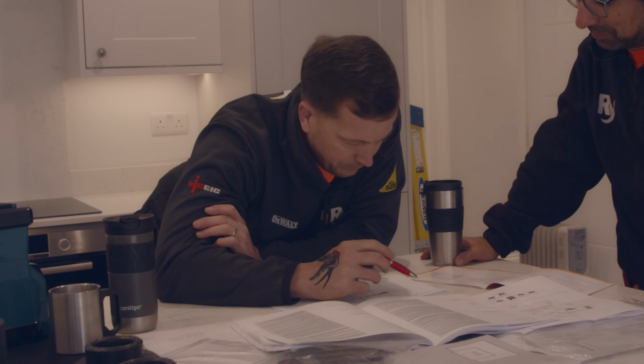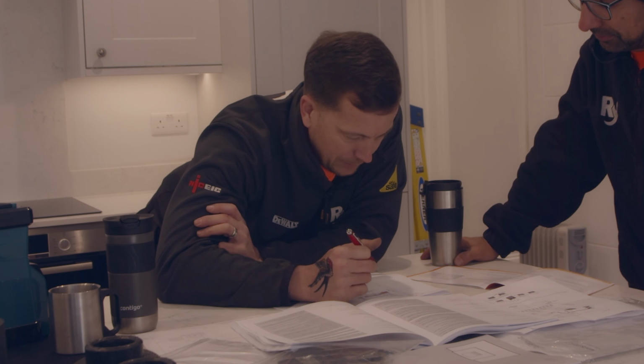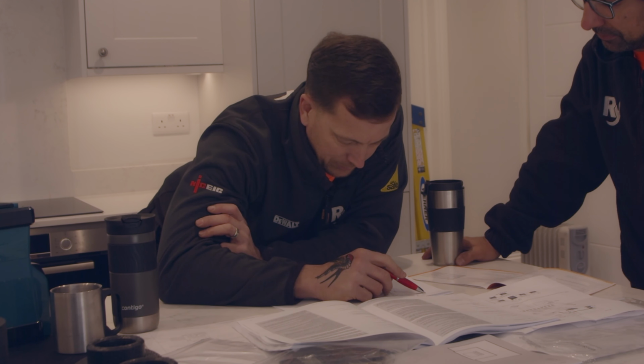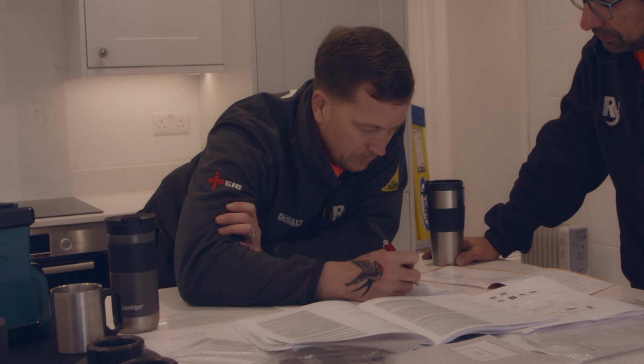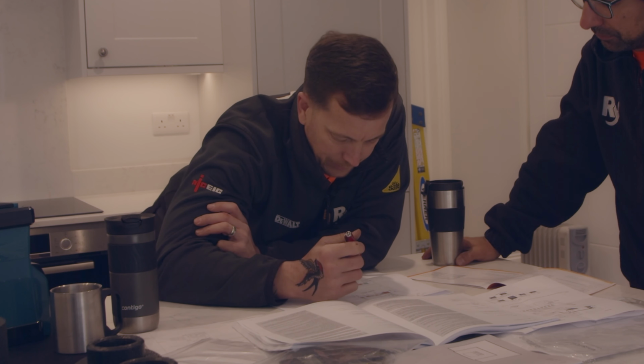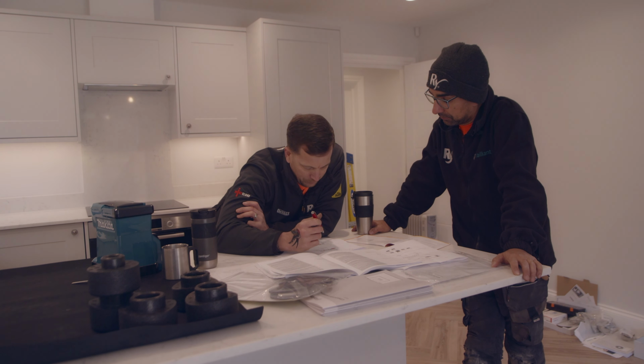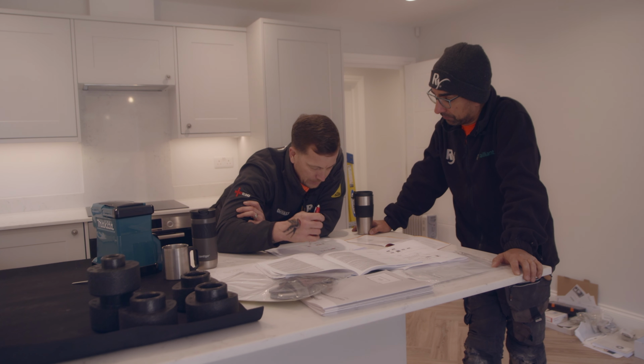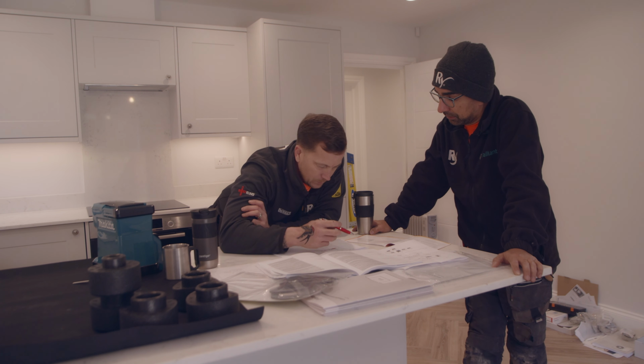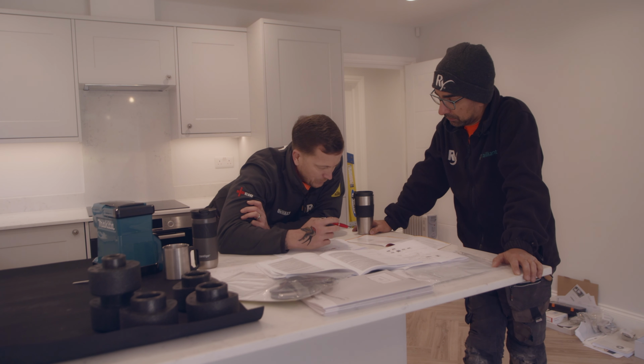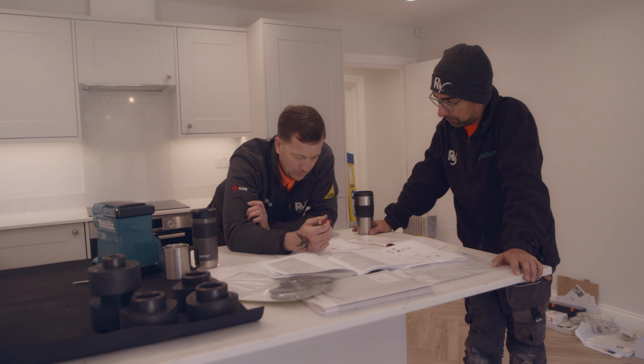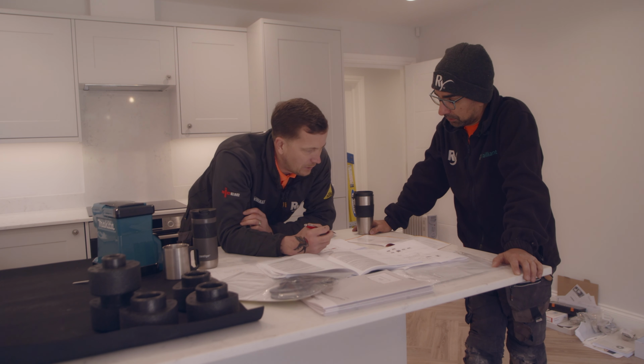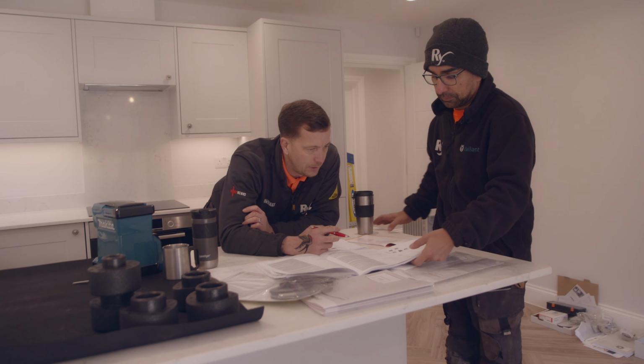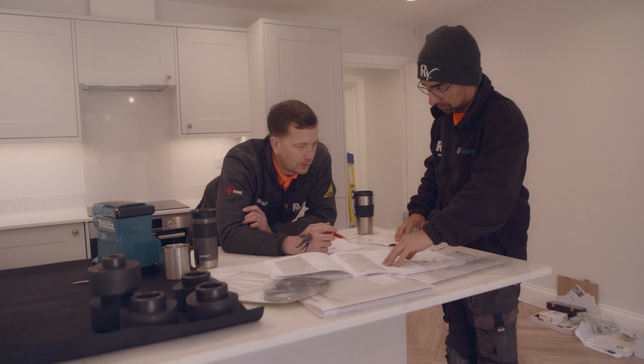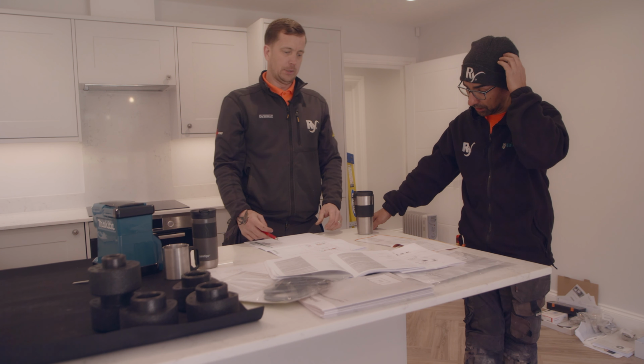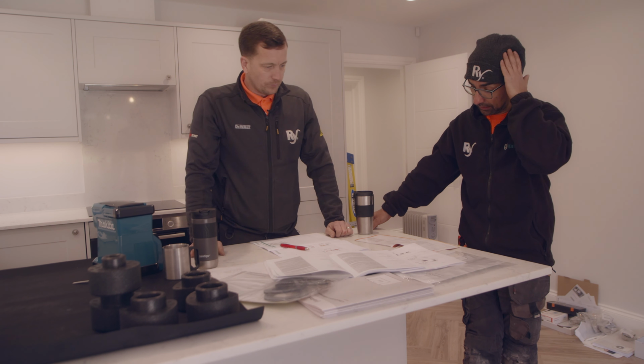After getting off the phone to Vaillant, they've cleared up that the diverter valve we've got is just going into UV1 on the interface, and the cylinder stat is going into SP1. We need to make sure the connections are tight, because it can break the signal, so we'll ferrule that. The underfloor heating one, which was really throwing us out, is going into the EVU via the volt-free connection, on the heat enabled setting, so that will give the signal and sort it out.